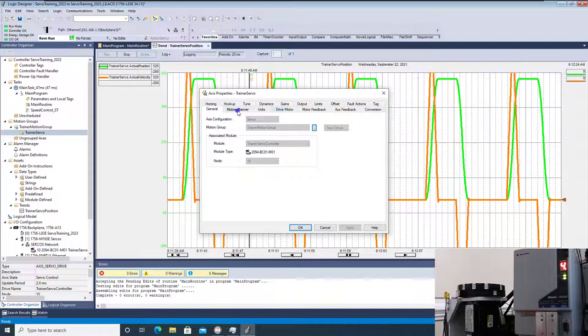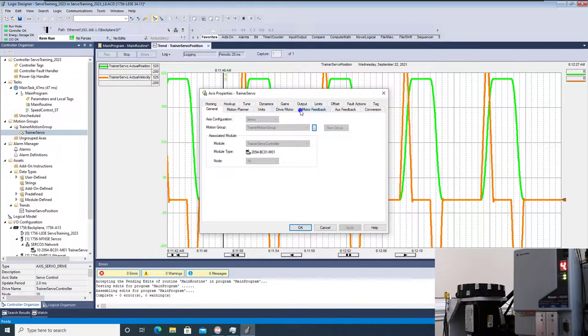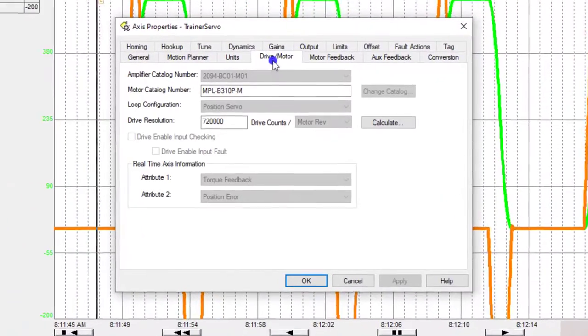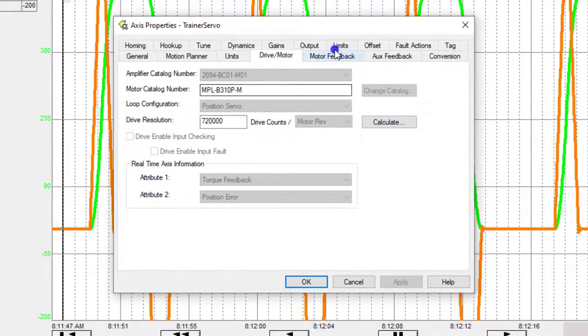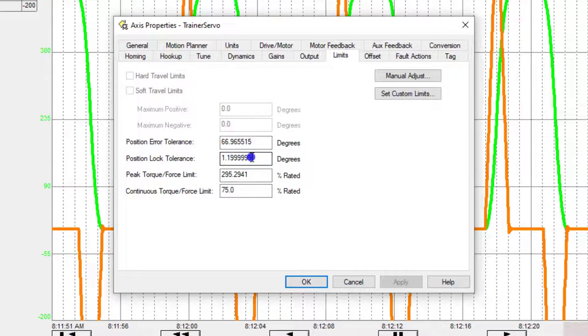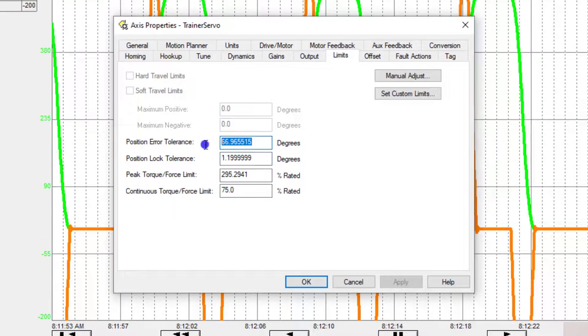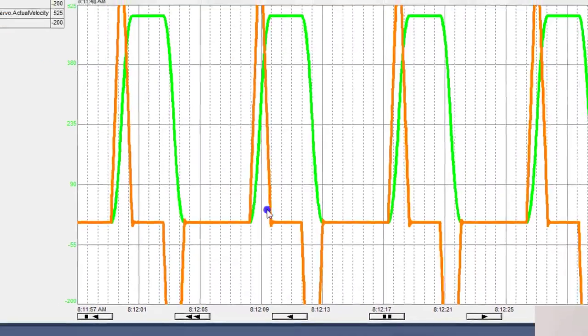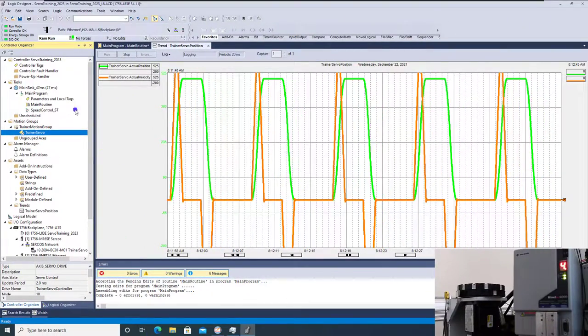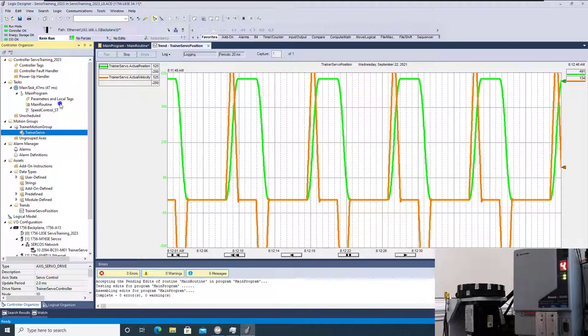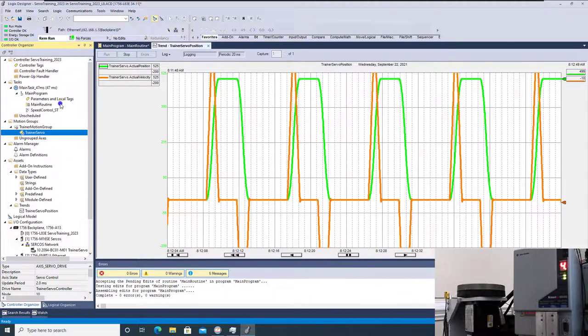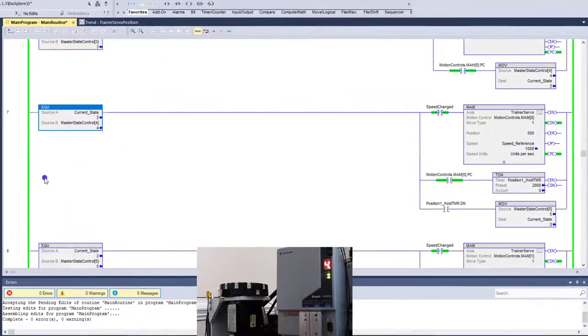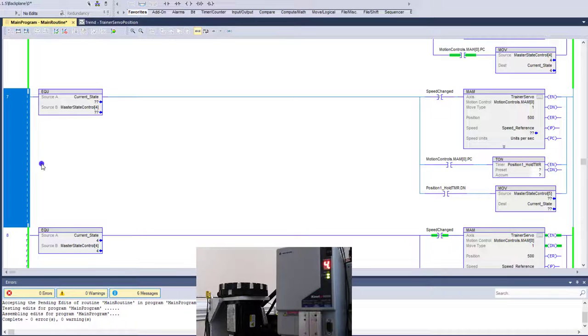Now that's based upon basically your faults and stuff of that nature. But keep in mind inside of your drive and stuff like that, you do have your limits. So currently the position lock is right here. We have our position error right here. So we're saying 66 degrees. Now, again, that's based upon my attributes. So please don't kind of get off in that tangent as much as when we're talking about getting into an S curve versus a trapezoid. So keep in mind the difference between the two.